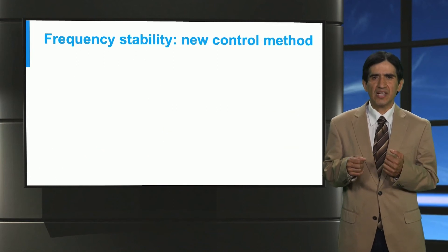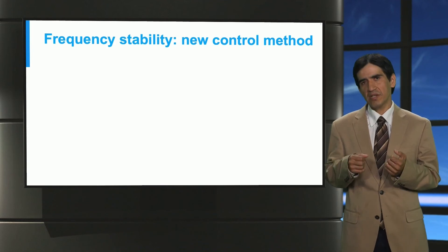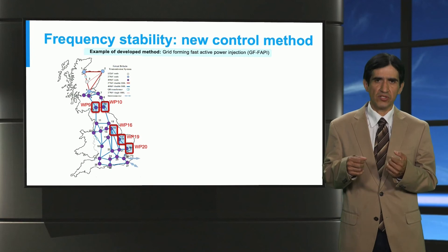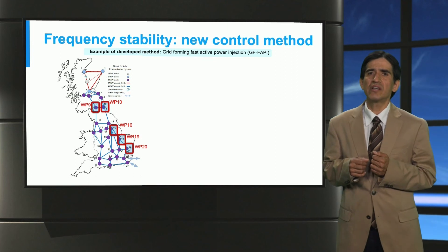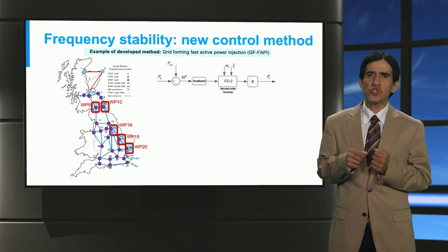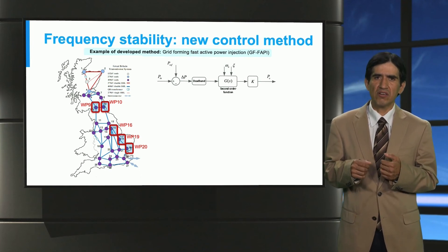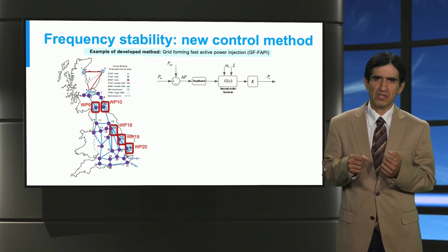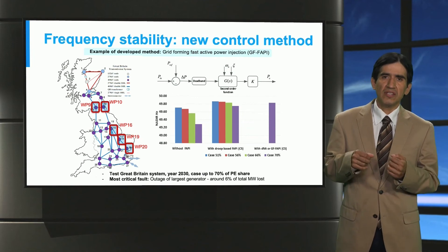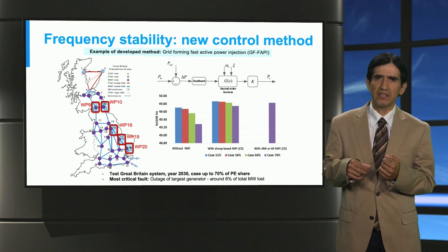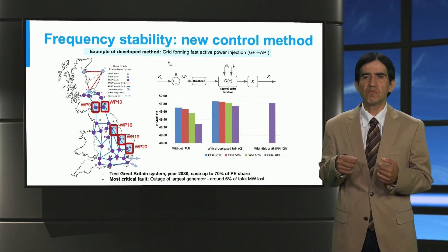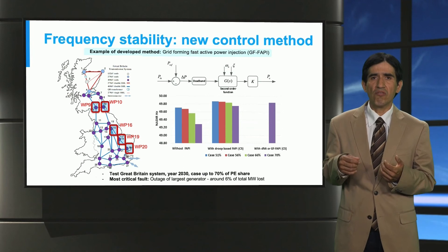Now, let's talk about example upgrades of control systems needed for secure operations. Firstly, we discuss a frequency stability new control method. This particular example concerns grid-forming fast active power injection. This emerging method is superimposed on the control structure of the grid side converter, with the goal of performing a very fast adjustment of the active power injection from a wind generator. This adjustment is done based on measured deviations of active power, which are passed through a deadband and a second order transfer function. Both functions are tuned on a system-dependent basis. The example, based on simulations conducted on a test system representing the Great Britain system, shows that an increase of wind generation share up to 70 percent can be feasible without having large under-frequency deviations, also known as frequency Nadir, if grid-forming fast active power injection is performed by a set of wind turbines, which can play a major role in the stabilization of the system frequency.